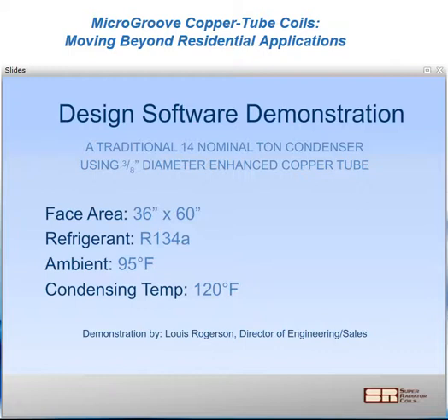Louis? Thanks, Matt. What we're going to look at today are a few different scenarios of how you might integrate 5mm into your existing rooftop condensing unit. For the unit we're going to evaluate, we'll start with a nominal 14-ton condenser using 3/8 tube. The coil we'll evaluate is 36 inches fin height by 60-inch fin length. Refrigerant is 134A, 95-degree ambient temperature, so that's rooftop most anywhere in North America, and we'll use a condensing temperature of 120 degrees F.